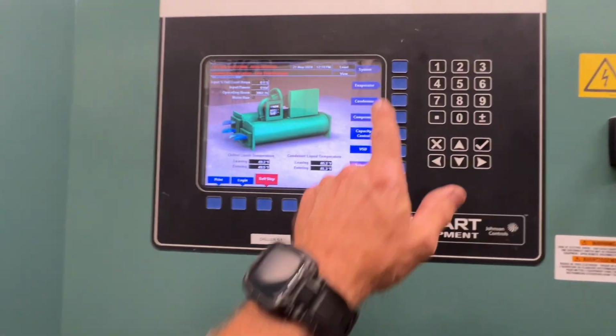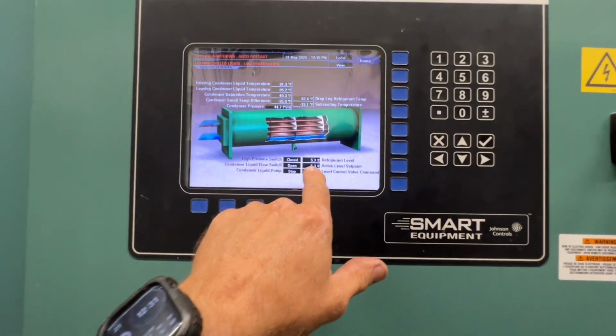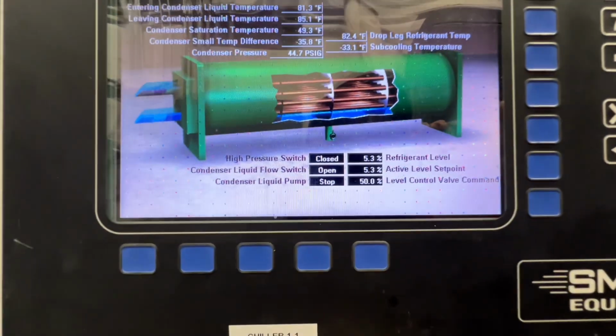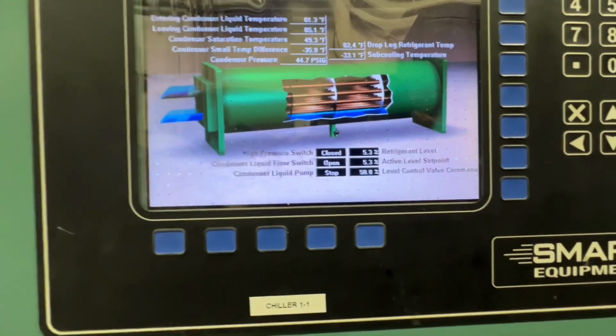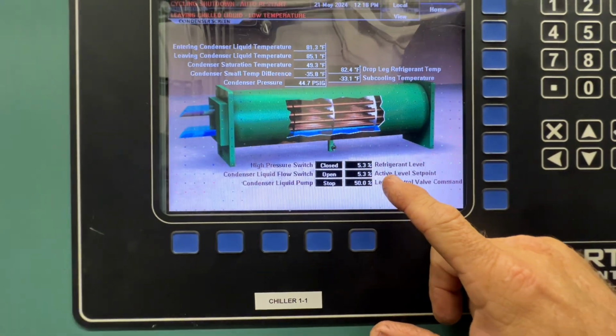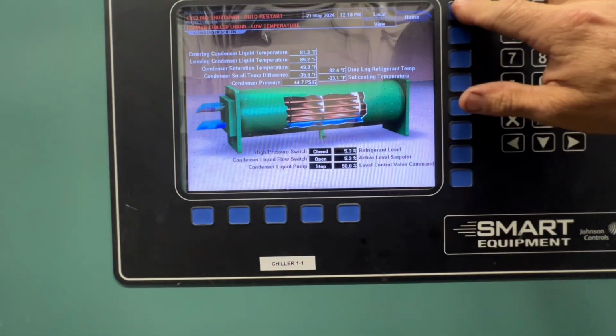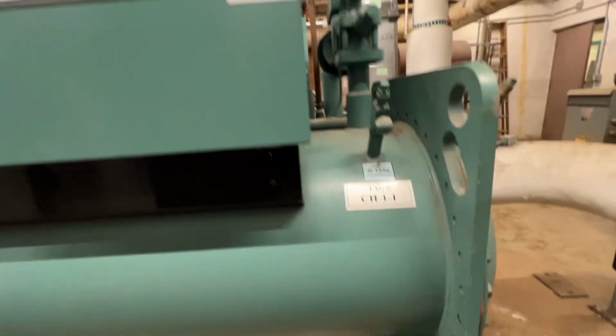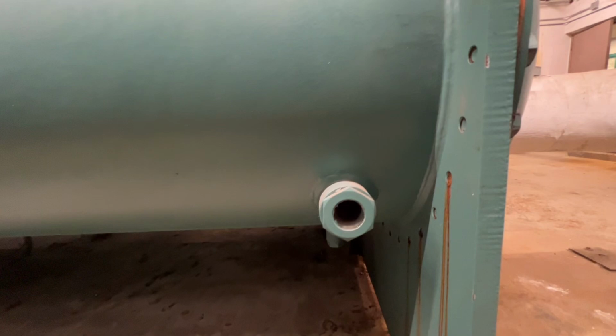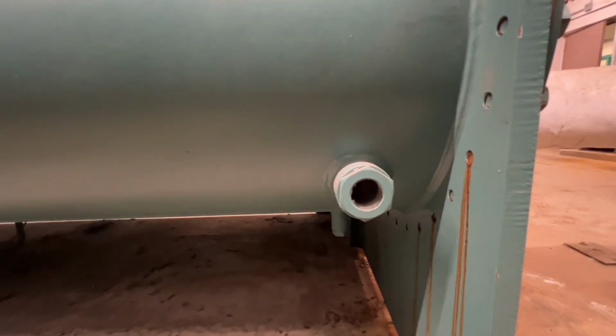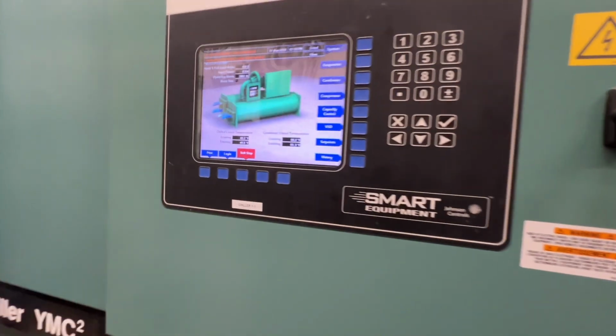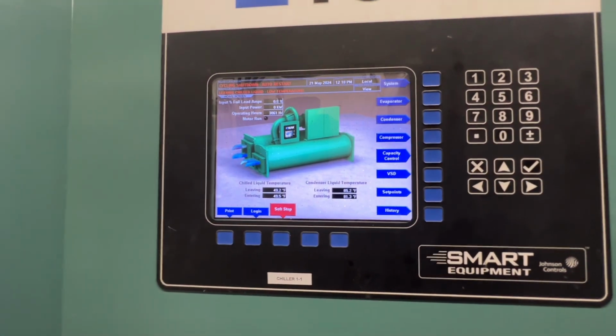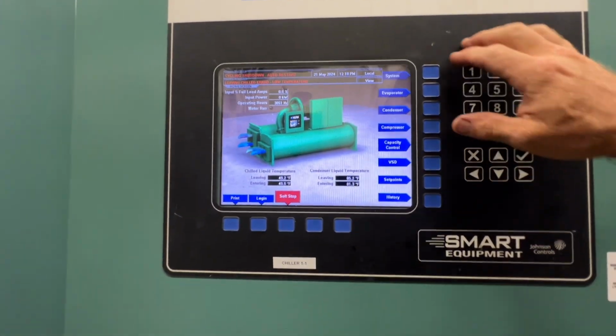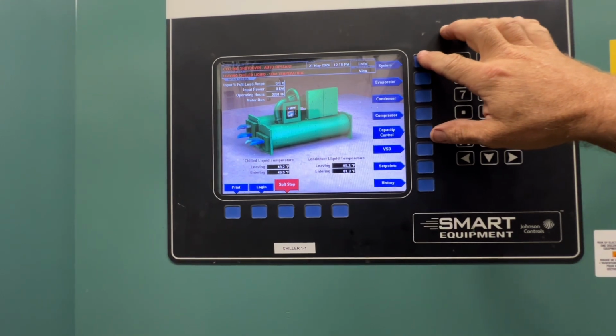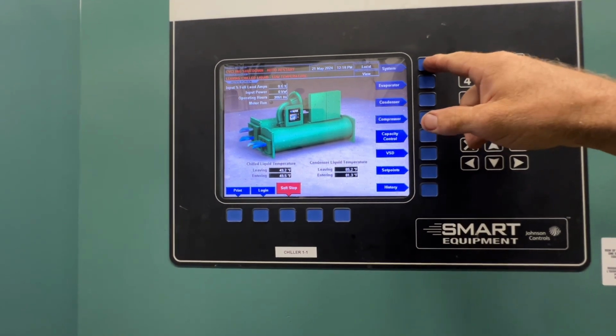One more thing. The condenser refrigerant level, right now it's off, so it's showing 5.3, but he raised it from 38% to 50%, and that made our level in here come back up over top of that subcooler, and I stopped getting that warning for the liquid subcooler seal loss. So that went away. Pretty much that's it for this one.